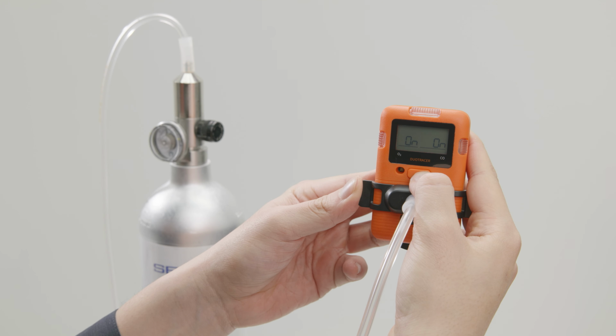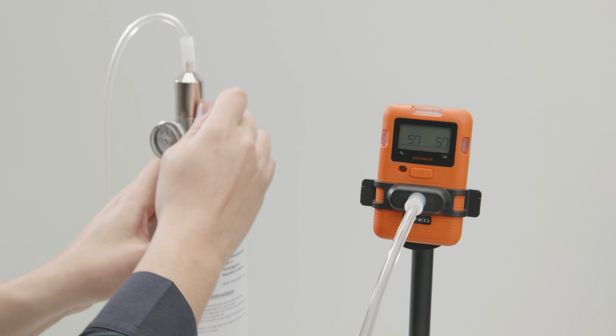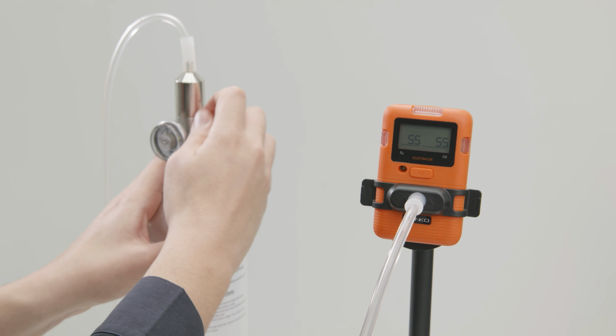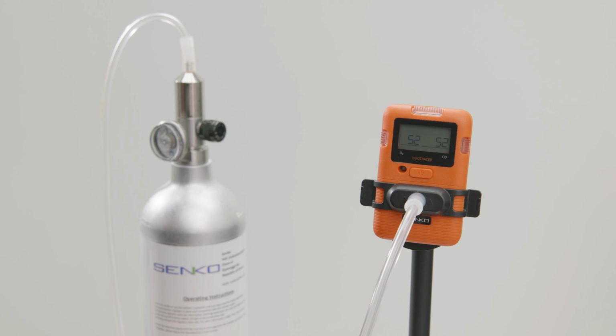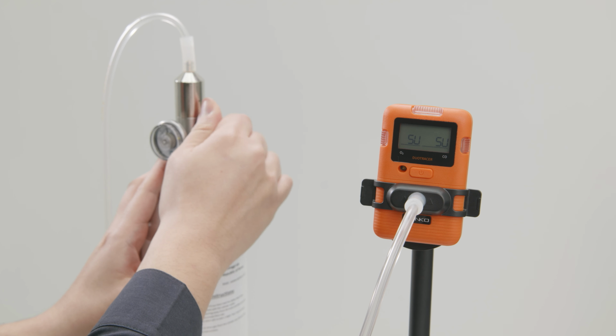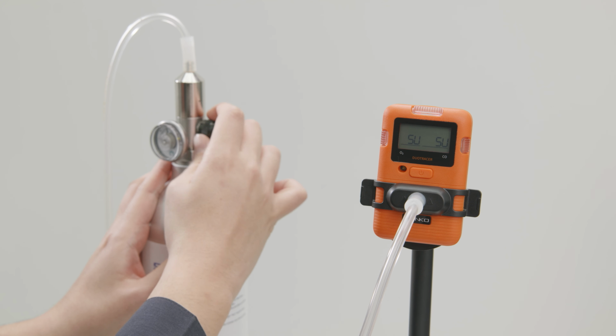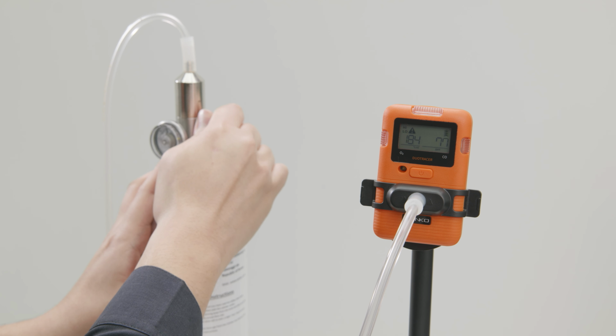First, enter bump test mode, select the gas channel you want to test, and press and hold the button to confirm your selection. Once the channel is selected, the bump test countdown starts, lasting about 60 seconds. During this time, apply standard test gas to the sensor inlet at a concentration slightly above the low alarm set point. If the sensor responds normally and the alarm activates as expected during the test, the bump test is considered a success. When the test is complete, the results will be shown on the LCD screen.